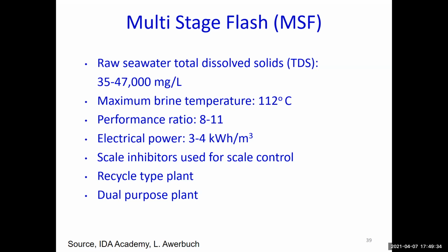Electric power is 3 to 4 kilowatt hours per cubic meter. People working with RO claim that all you need is something like 2.2 or 2.3 kilowatt hours to desalinate the water. Making a simple comparison, without heating, the electrical power needed for the MSF is much more than that, and it can run an RO system for desalination. And that is actually what has been driving the SWCC here in the kingdom to move into the idea of RO.